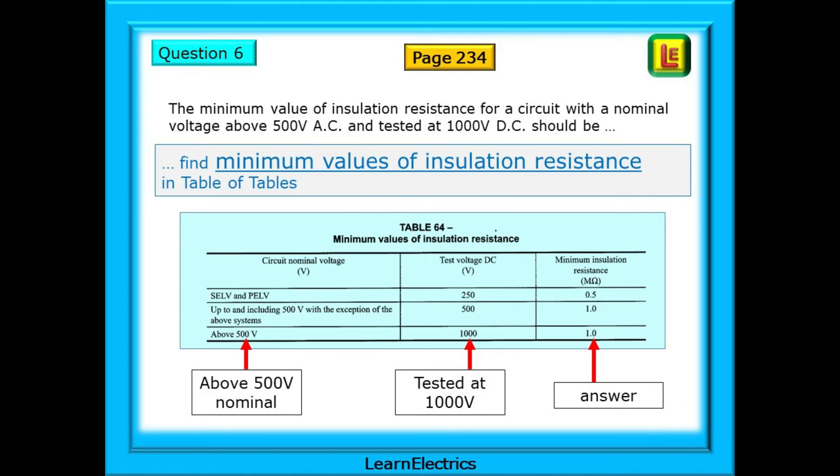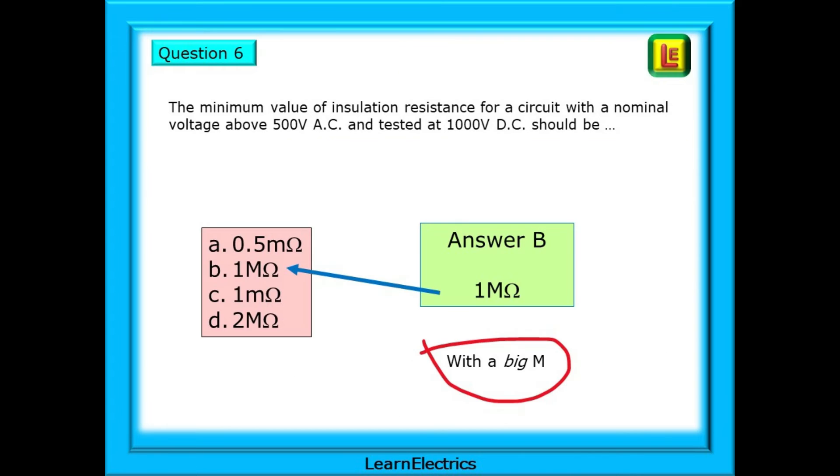We should know that this question is to do with testing, and that testing is part 6 of the Brown Book. Looking through table of tables, there is only one entry for part 6, and this is table 64, minimum values of insulation resistance. Just what we're looking for. Go to page 234. Again, break the question down into discrete pieces of information. Above 500 volts, find that row, and test it at 1000 volts. The last column gives us the answer, 1 megaohm of resistance. Now choose an answer, and we should go for answer B, 1 megaohm.